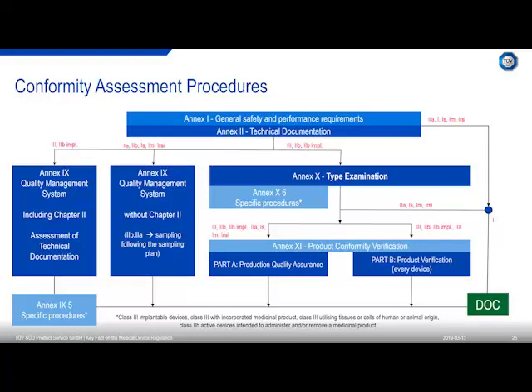If you want to do testing with a notified body, so do a type examination, then that's possible for class 3 implantable, and then you go through Annex 10 type examination. And depending on the risk class, you also need to take into consideration Annex 10.6, which is special procedures. They are applicable, as I said here, for implantable devices and devices with incorporated medicinal products, or class 3 utilizing tissue or cells. So there are special procedures that you need to follow. Otherwise, you can go through the product quality assurance or through product verification.